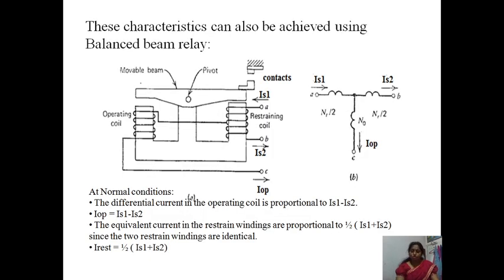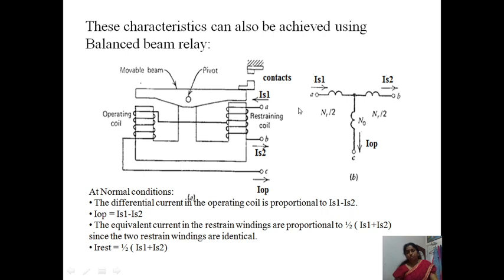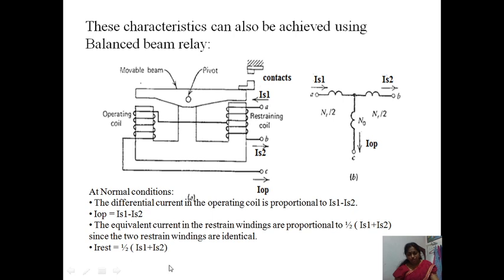This characteristic can also be achieved using a balanced beam relay. Here you can see the operating coil and the restraining coil, which is divided into two halves. The midpoint is connected to the operating coil — the same structure as before, only the balanced beam structure is used. It is shown with currents I1 and I2. At normal conditions, the differential current in the operating coil is proportional to I1 minus I2, while the restraining torque is produced by (I1 + I2)/2.